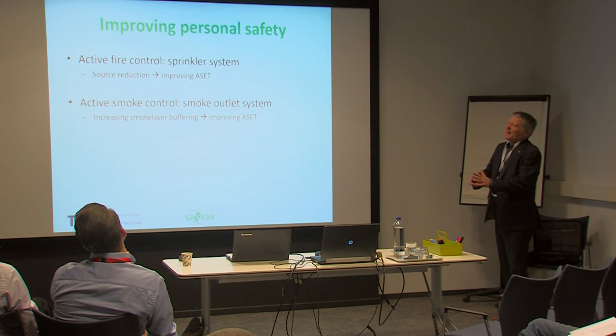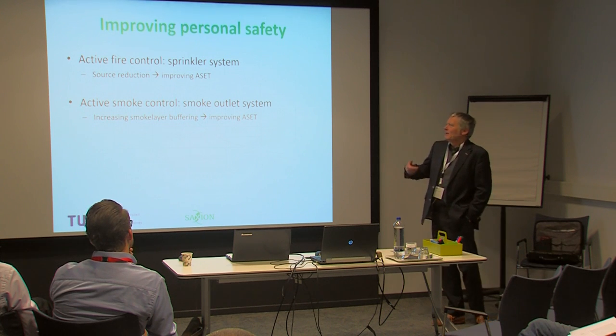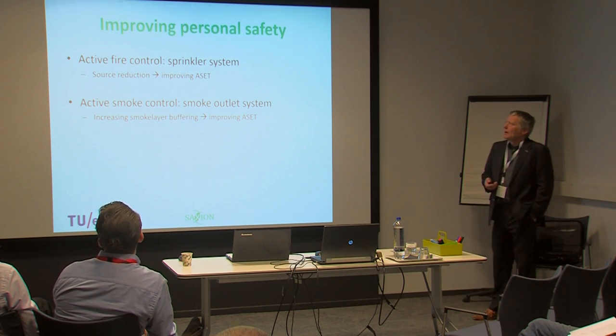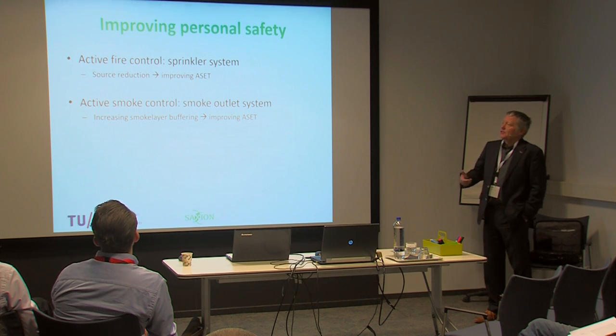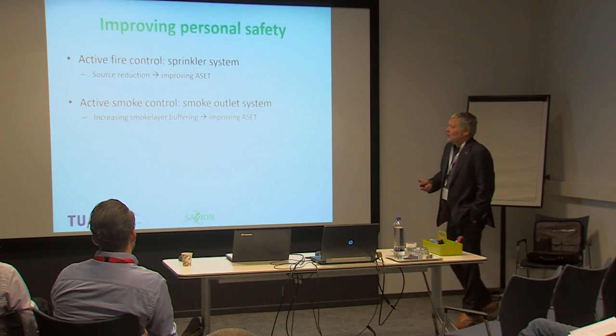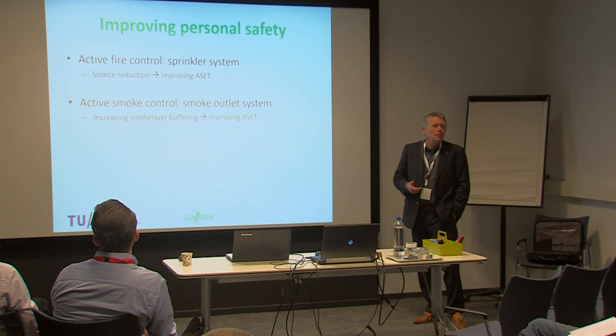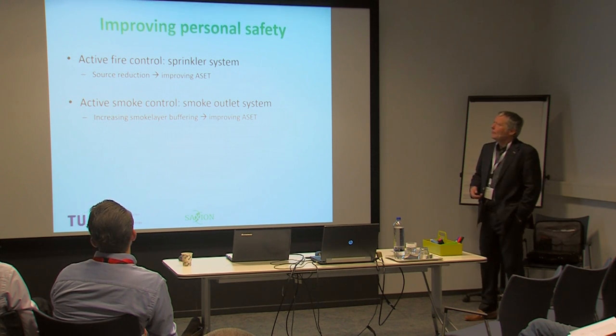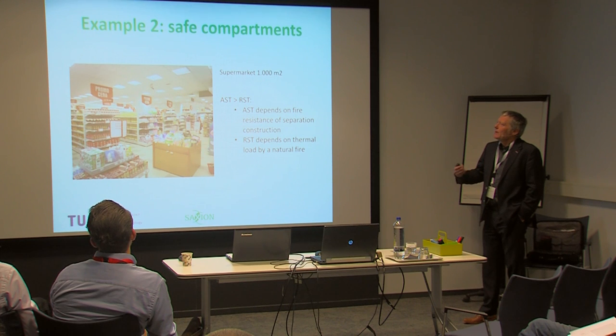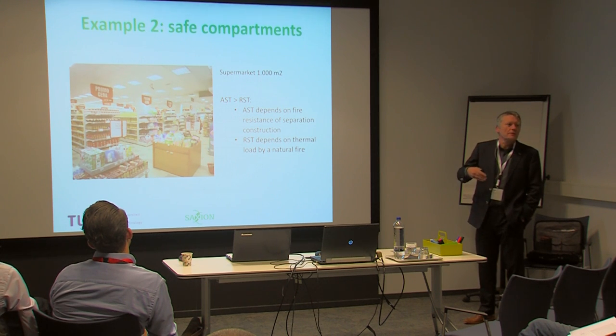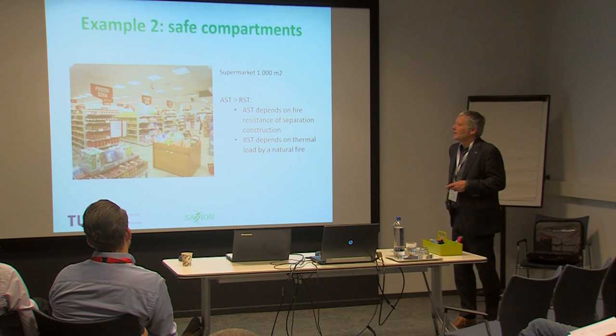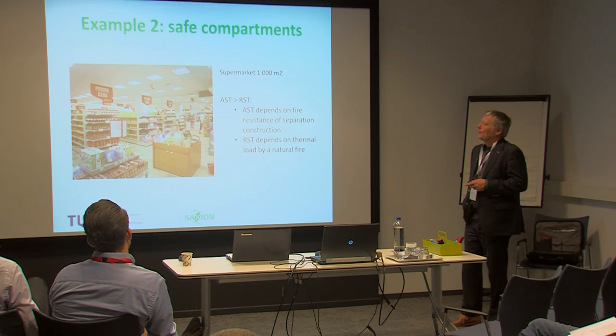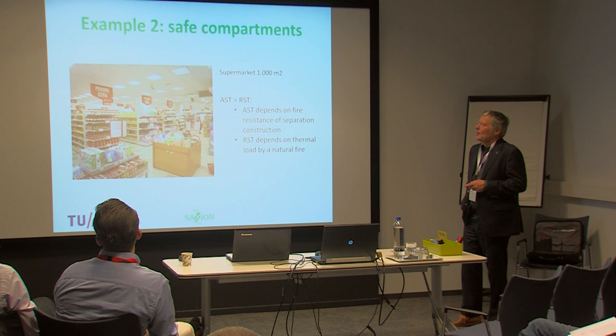To achieve a slightly higher safety level in this case, you can think about active fire control with a sprinkler system, active smoke control with a smoke outlet system to increase smoke layer buffering, or theoretically also compartmentation — though that's not desirable for a market hall. We do a lot of projects with the ASET/RSET definition, and we can do the same for compartment walls.